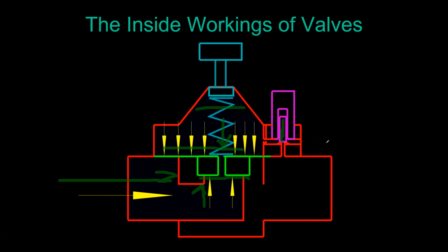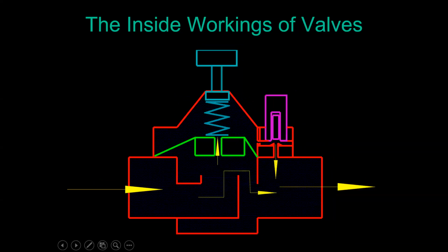So what happens is when the timer sends a signal to the valve, it opens up this port right here, and the water from the top chamber goes out the top side of the valve downstream. Now there's less pressure up top here, and now the water itself is what pushes that diaphragm in the up position. Let's erase those real quick and show you what it looks like at that point. Oops, I didn't get rid of my rotation bar there. So here we go. That's what it looks like when it's open.